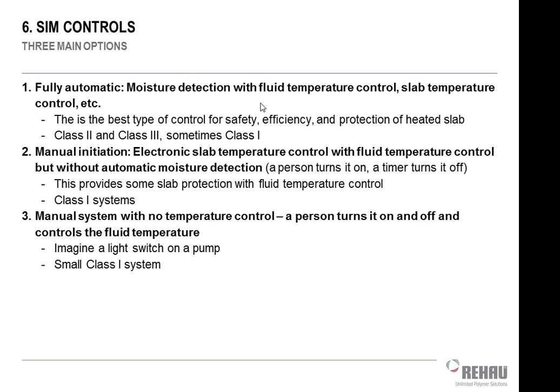and if snow falls in the electric grid, the wetness of the snow completes the electric grid's connection, so it knows that it has moisture and thereby allows the system to be enabled, but it also has to be below a certain temperature. So it's got to be below, say, 39 degrees outside, and I have to detect moisture, then I'm going to turn the snowmelt on. If it's above 39 and I detect moisture, I'm just going to assume that it's rain or that it's snow that's going to melt off very quickly because it's so warm outside. If it's below 39 or 37, whatever number you pick, then I know that it has the potential for freezing on your driveway or your sidewalk, so I'm going to go ahead and run the system.